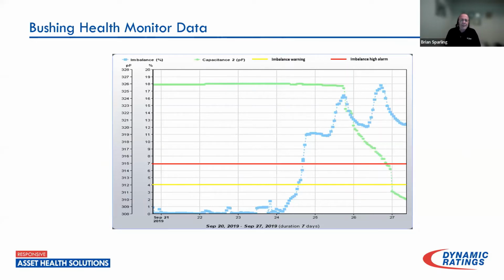But looking at the data, you can see here that, and we found this, changes in bushing condition can happen over a relatively short period of time. In this case, we're looking at the light blue trace, which is the total imbalance current of all 3 bushings, and you can see it's where it should be. It's fairly stable, but on the 24th, it begins to increase, and increase quite a bit. And the green trace is the calculated capacitance in picofarad of the bushing. So we can see here, as imbalance current is increasing on this phase, the capacitance value is decreasing on the bushing.